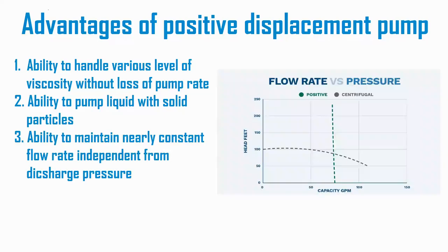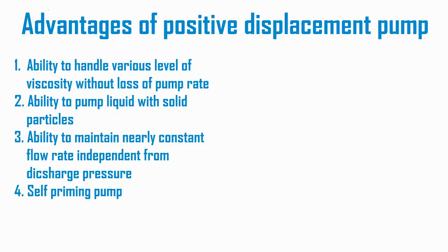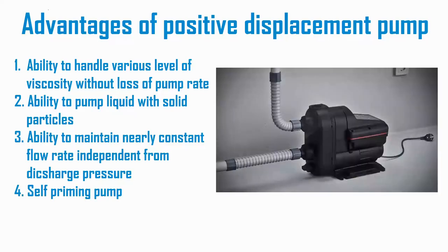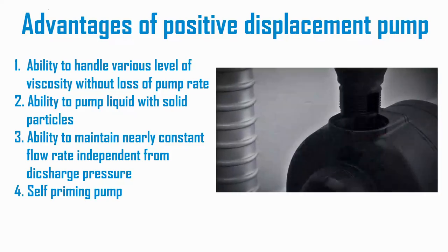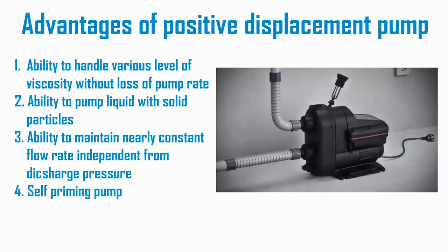The rotary positive displacement pump has a constant flow rate — the flow rate is always constant as long as the drive is still strong enough, and it is independent of the pressure on the discharge side of the pump. The rotary positive displacement pump is also a self-priming pump, meaning there is no need to fill it with liquid to start the pump.